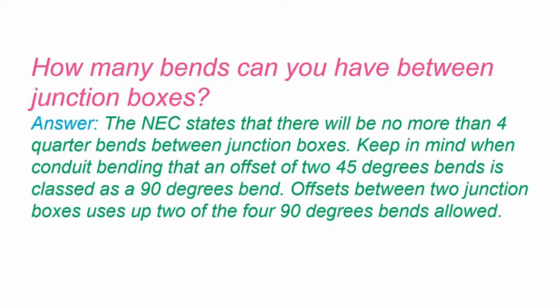How many bends can you have between junction boxes? Answer. The NEC, or National Electrical Code, states that there will be no more than four quarter bends, or 360 degrees, between junction boxes. Keep in mind when conduit bending, an offset of two 45 degree bends is classed as a 90 degree bend. An offset between two junction boxes uses up two of the four 90 degree bends allowed.